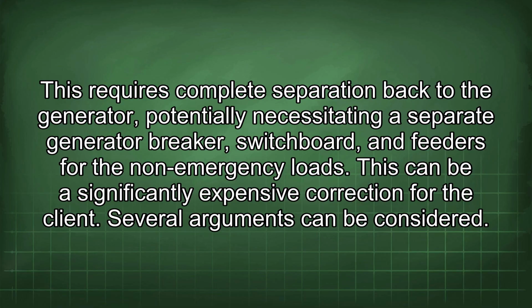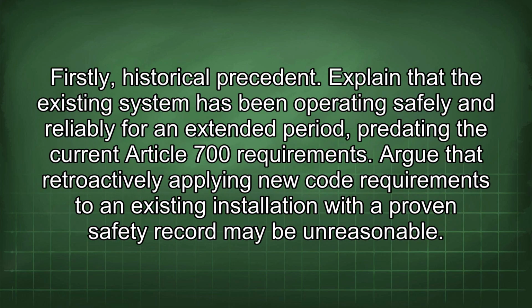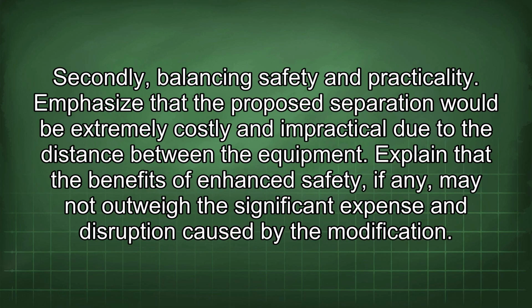Several arguments can be considered. Firstly, historical precedent. Explain that the existing system has been operating safely and reliably for an extended period, predating the current Article 700 requirements. Argue that retroactively applying new code requirements to an existing installation with a proven safety record may be unreasonable. Secondly, balancing safety and practicality. Emphasize that the proposed separation would be extremely costly and impractical due to the distance between the equipment.